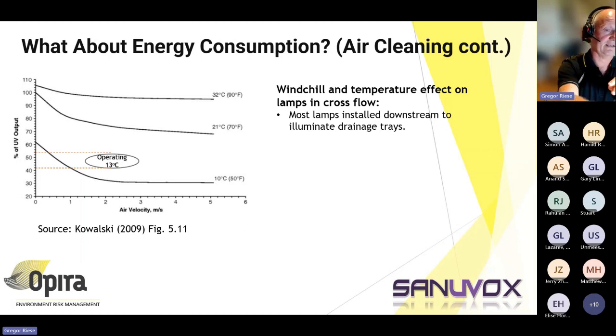If you're running your air handler at 13 degrees Celsius, the lamp will still suck all the power that it always does, but it will not give you the UVC output of something operating at 21 degrees Celsius. It halves. In fact, Sanuvox recommends for coils that you place the UV installation upstream. The best practice is placing the UVC installation upstream. We need far fewer lamps and you use far less power, and the UVC still goes through the coil, so you don't put it downstream of the coil. Now, most customers want it downstream of the coil because you've got the tray there, you've got the water accumulating there, and that is also irradiated and stays clean.